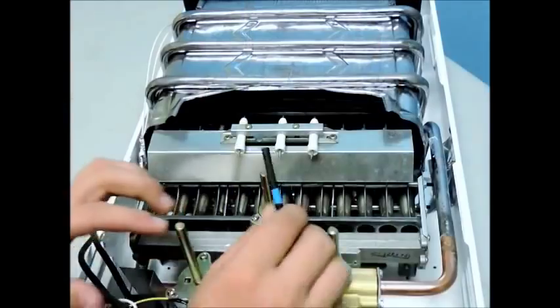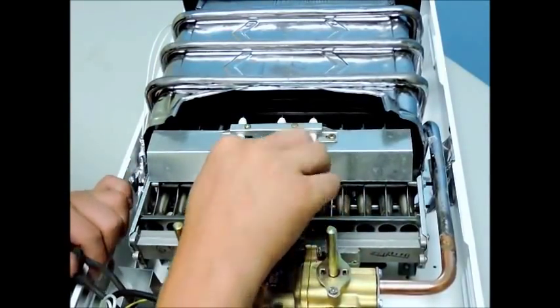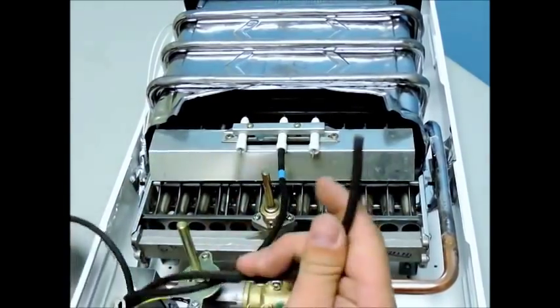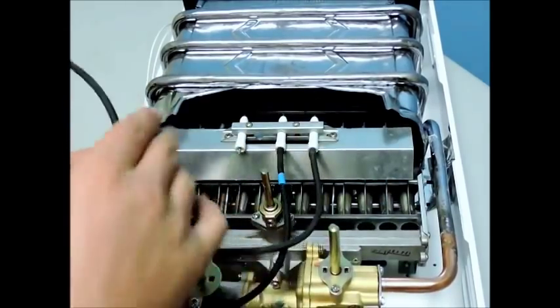Now you are ready to reconnect the three black wires that we removed previously. Please note that the black wire with the blue tape needs to be connected to your thermocouple sensor which is located in the middle between the two igniters.